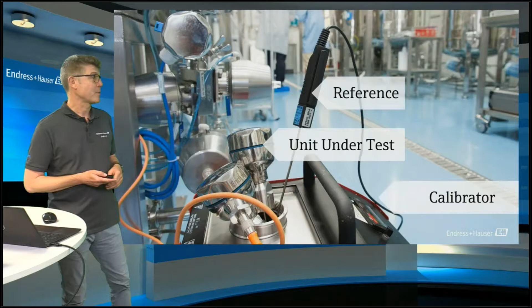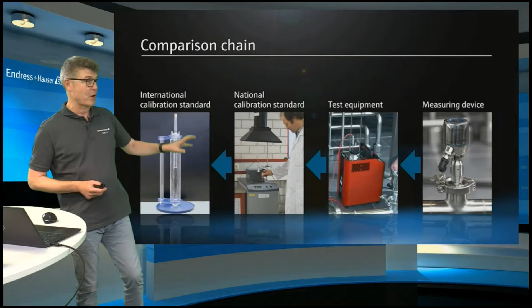All right. So the typical calibration process can be seen also in this short animation. The comparison chain, the traceability of the calibration: your device under test must be calibrated using some test equipment, maybe on site by your service team, by maybe you, or by an external company. The test equipment itself needs to be calibrated too. For this, the next step is a national certified laboratory, like we operate here at our site in South Germany, accredited by the state. And the state itself operates a national institute, and all the national institutes work together. So, coming from a fixed point, the international calibration standard, this trace of accuracy and uncertainty goes to the measuring device itself.